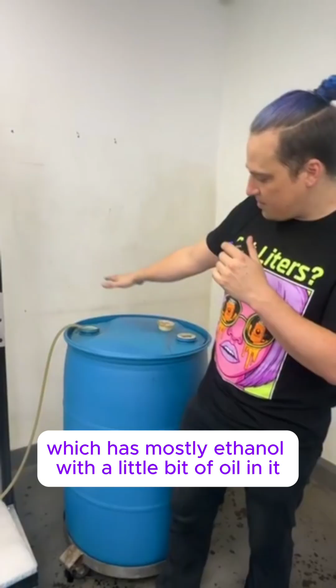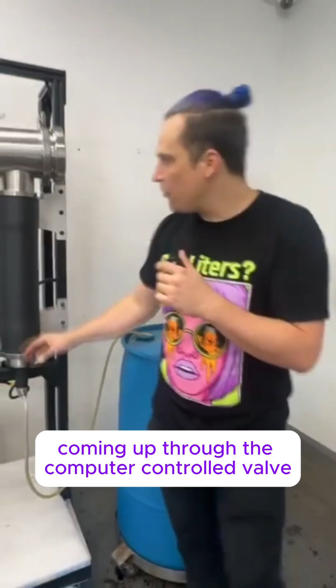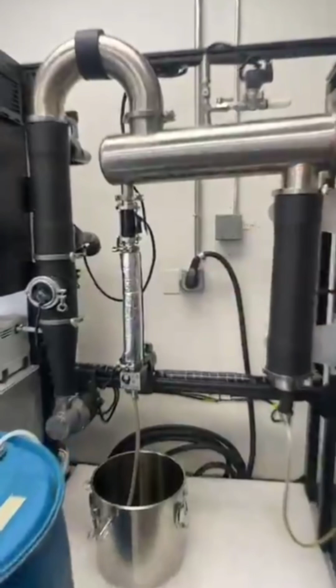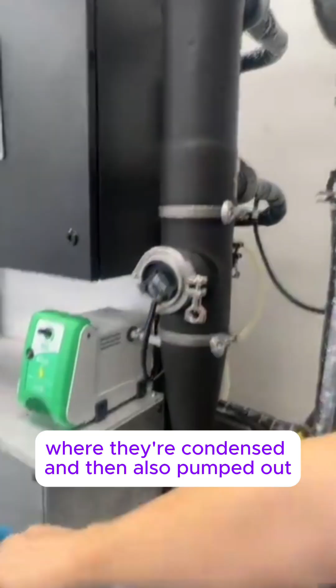This is the evaporator section. So we're feeding from this barrel, which has mostly ethanol with a little bit of oil in it, coming up through the computer controlled valve into the liquid separator where the unevaporated oil flows out and collects here and can get discharged by the oil pump. And then the vapors come over the top here to the condenser where they're condensed and then also pumped out.